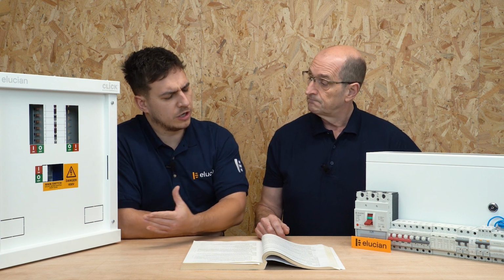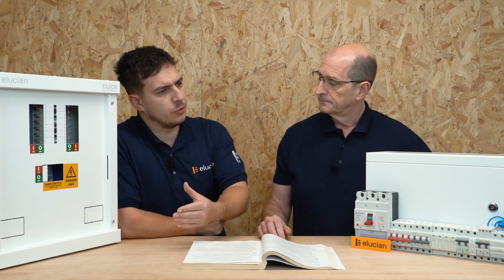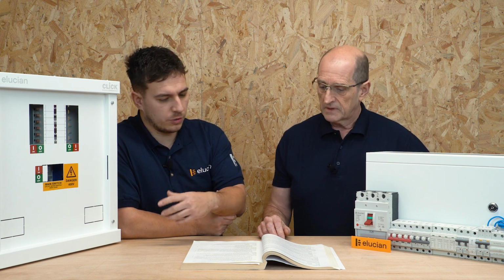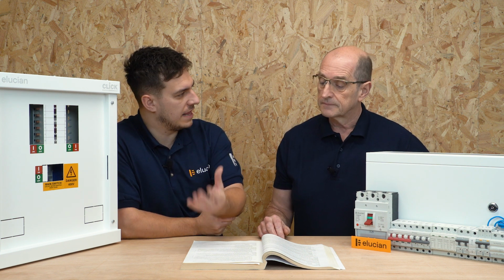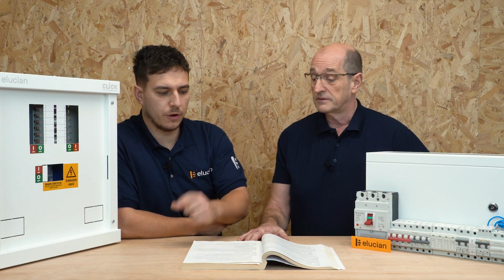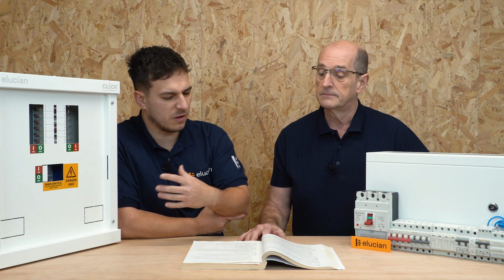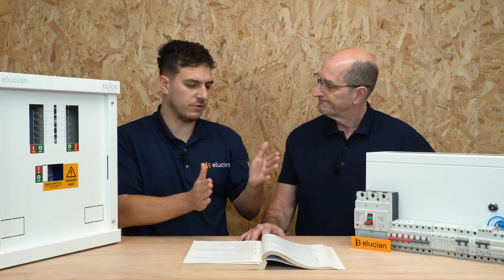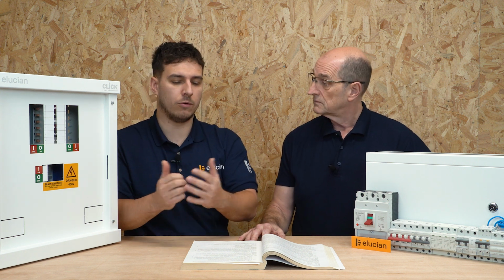So going back to the threshold, what's the threshold of these devices? What level of DC can they cope with? Generally, we start at around 10 milliamps. It's the threshold that it does, whereas a Type A will be 6 milliamp. So we've got a little bit of increase there as well. A lot of people will look at that, Tim, and go, that's the reason why I need a Type B, because it can handle more DC. But we've also just given you a complete list of things and the reasons why, because of the nature of the connected load, we need to select a different type of RCD.